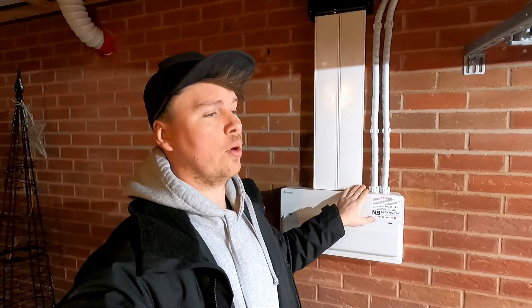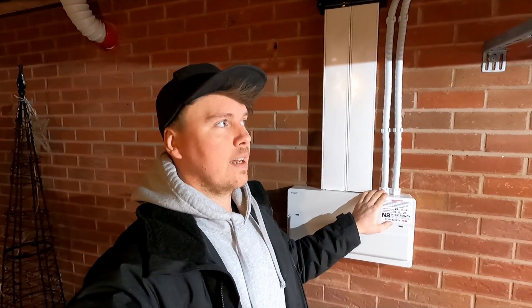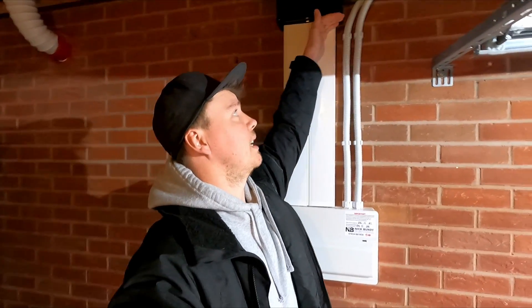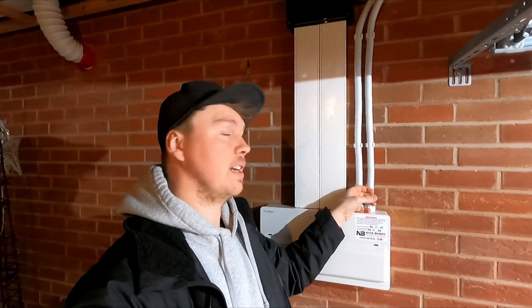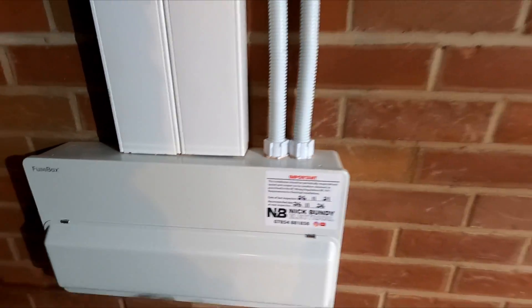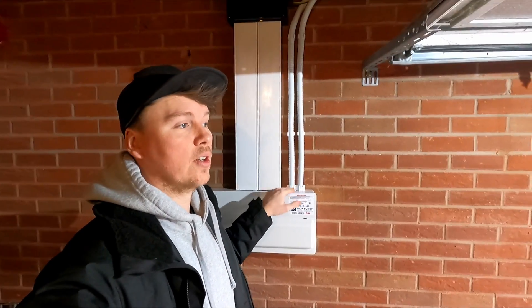What I'm going to do today - because I've looked into it a bit more and spoken to a good mate Dave Savory - I'm going to change this. I'm going to rip out the flexicon up to here, make the slot a little bit bigger in the board itself, and put the live and neutral straight through, also pulling the earth through. I've always known you put live, neutral and earth all the way through together in a stuffing gland - I just didn't have the space here because of the knockout sizes. This is why I want your opinion: will it make any difference whatsoever? Was what I've done correct or incorrect?